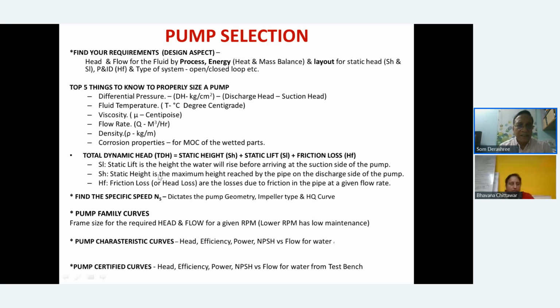And the static height is the maximum height reached by the pipe on the discharge side of the pump. So that is the static height. That is the elevation it has to discharge to. And HF is the friction head in all the pipes and pipe fittings, etc. Pipes and pipe fittings that you have, bends and reducers or any flanges or even valves or control valves, etc. You'll have a lot of losses happening. So all this put together gives you the total dynamic head.